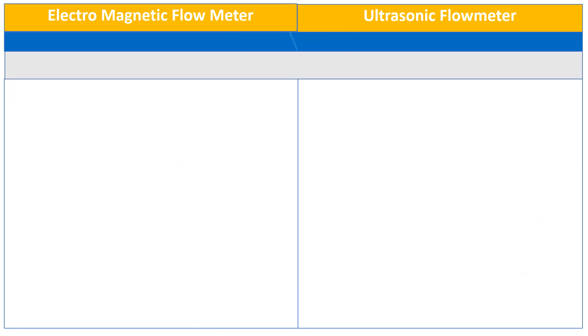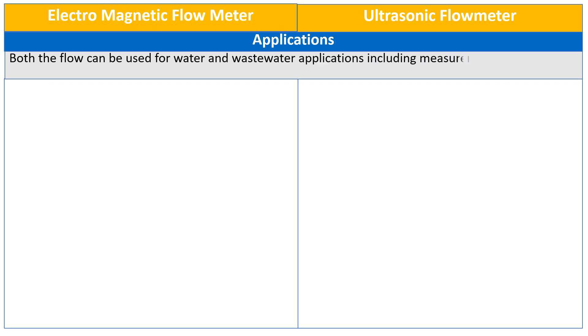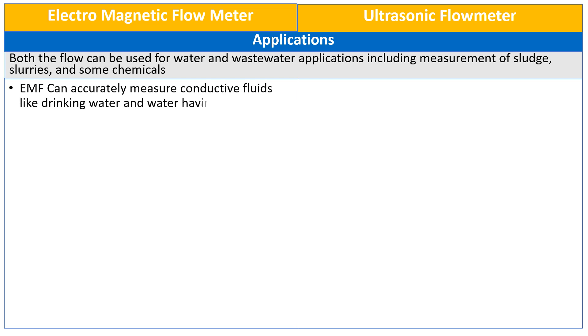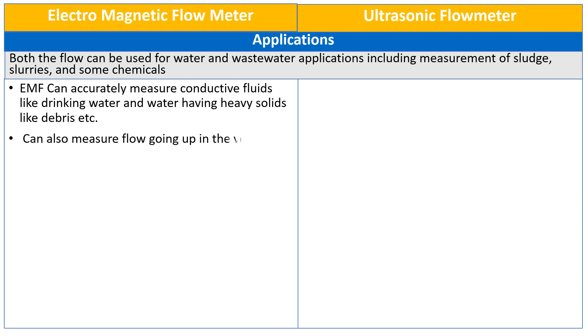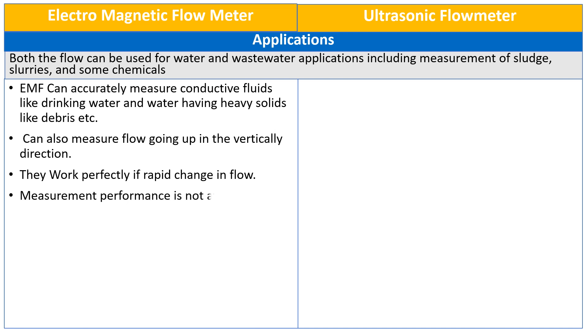Let us see the applications of electromagnetic and ultrasonic flow meters. Both flow meters can be used for water and wastewater applications, including measurement of slurries and some chemicals. The electromagnetic flow meter can accurately measure conductive fluids like drinking water and water having solids like debris. It can also measure flow going upward in the vertical direction. It works perfectly if there is a rapid change in the flow, and its measurement performance is not affected by the temperature, pressure, or viscosity of the fluid.